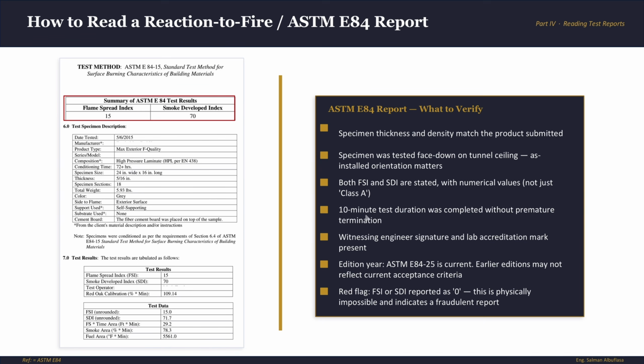And then the 10-minute test duration must be completed without premature termination. The full test is 10 minutes, mandatory. Any earlier termination invalidates the whole result. The report must confirm the full duration until completion.